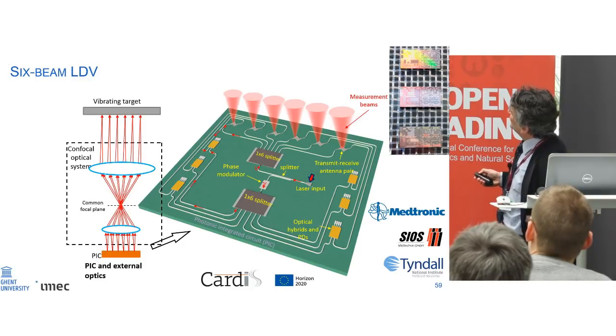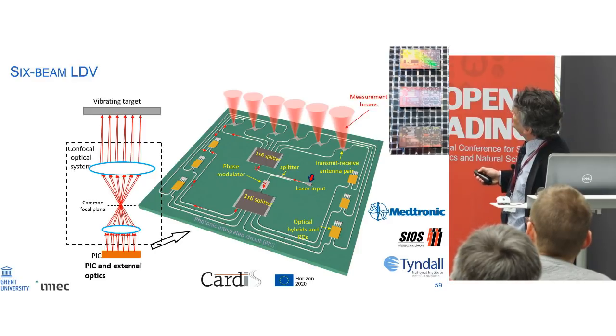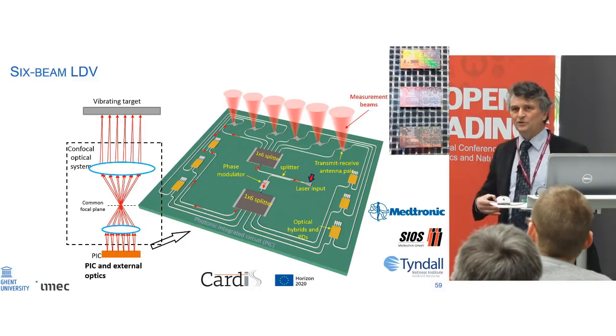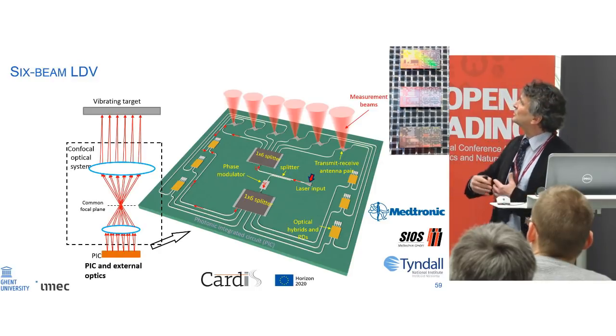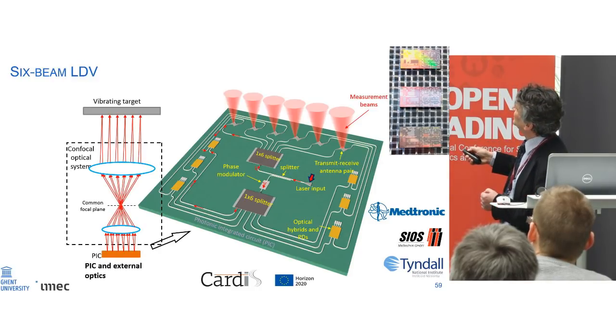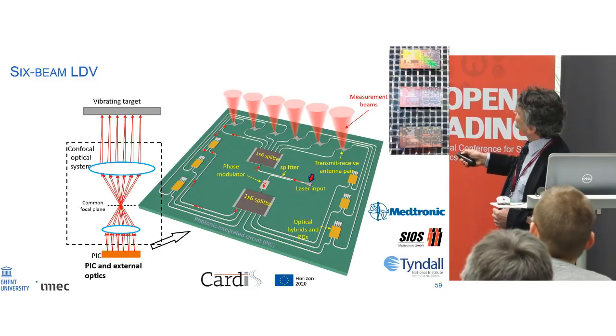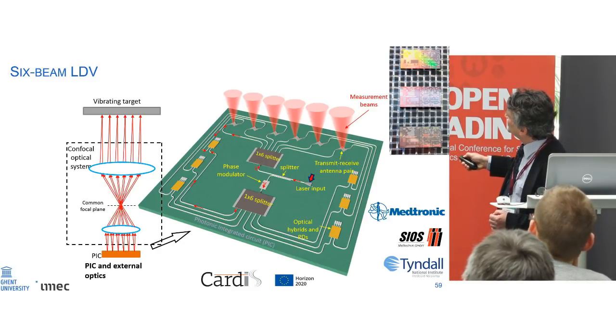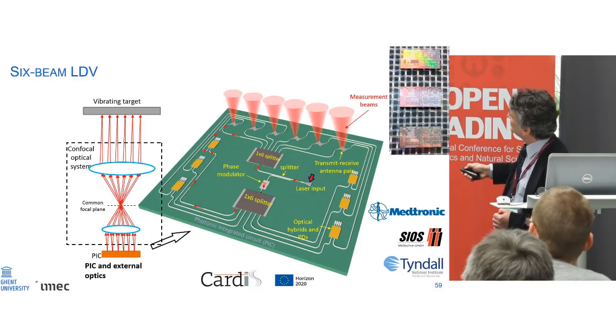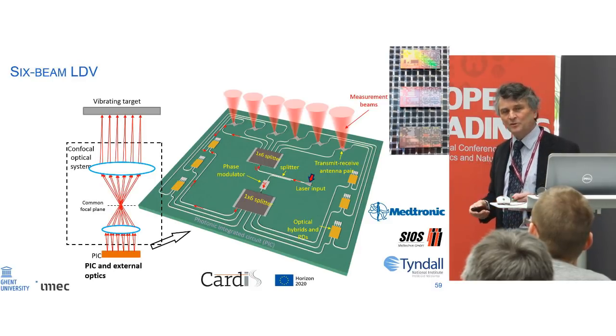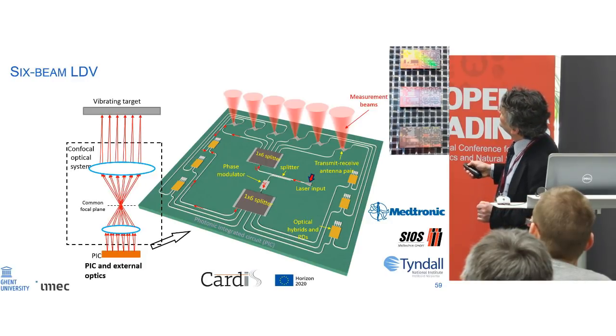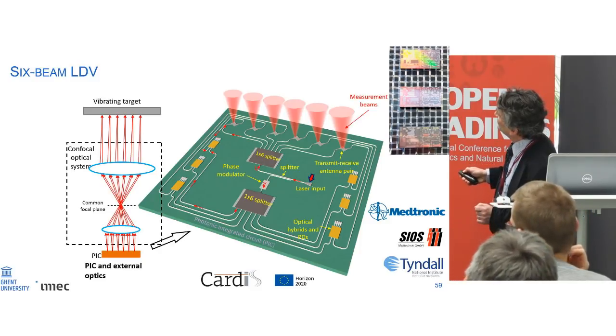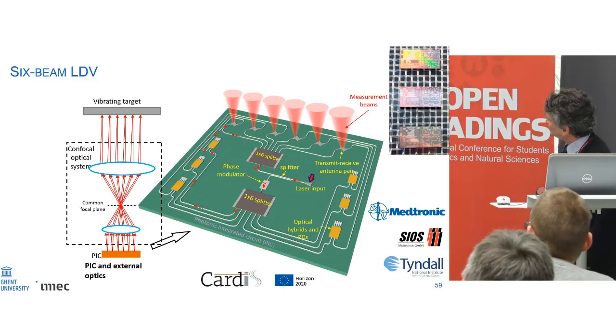In this chip, the laser is sitting here, and that will be an integrated laser with time. It's split into six channels here. At some point, six beams leave the chip and shine onto a moving target. All the reflections come back, picked up in the same place through an imaging system, and then the signals go further. You may have seen that here we split off part of the laser light, again by six, to have all our reference signals for the homodyne approach. We recombine the signals from each of these channels with the reference signal, then go to a detector and then to electronics.